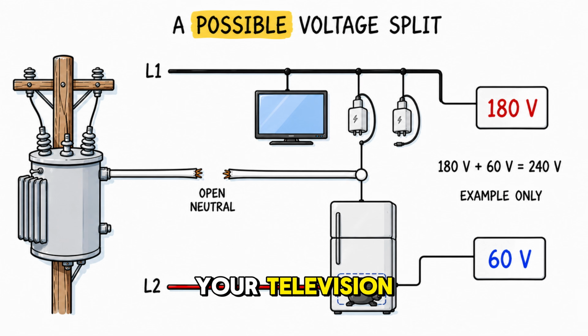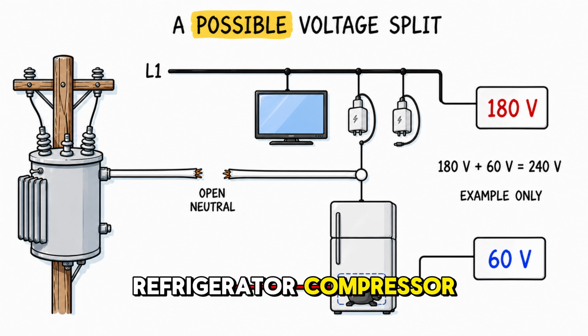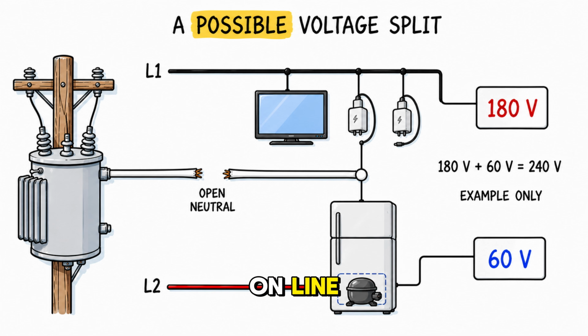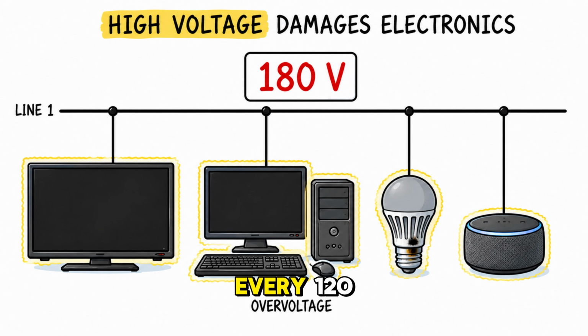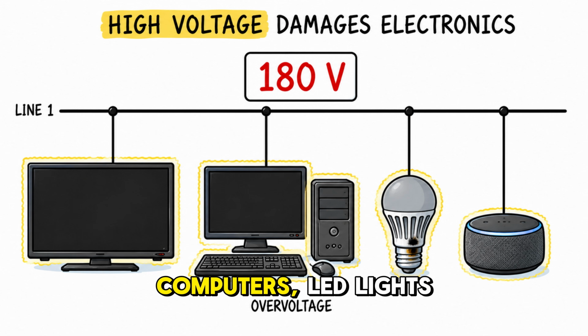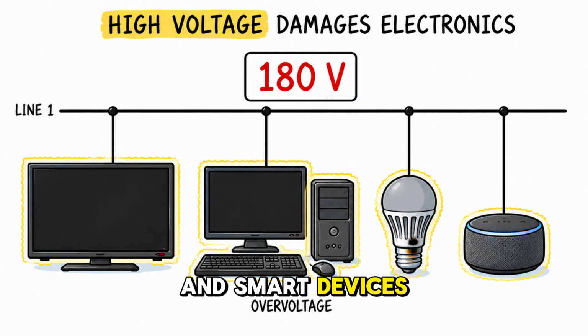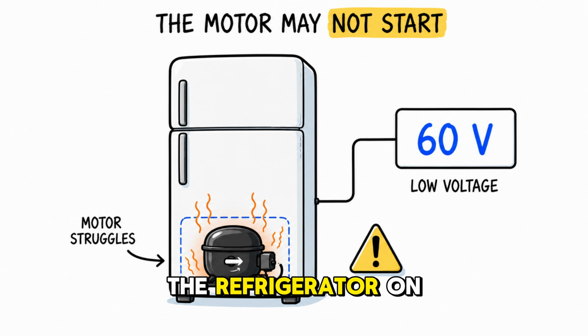For example, if your television and phone chargers are running on line 1, and your heavy refrigerator compressor kicks on line 2, the voltage on line 1 could easily rise to 180 or 190 volts. Every 120-volt appliance on that side suddenly receives nearly double its rated voltage. Televisions, computers, LED lights, and smart devices will burn out within seconds. At the exact same time, the refrigerator on line 2 receives only 50 or 60 volts. The motor struggles to start and begins to overheat from undervoltage starvation.